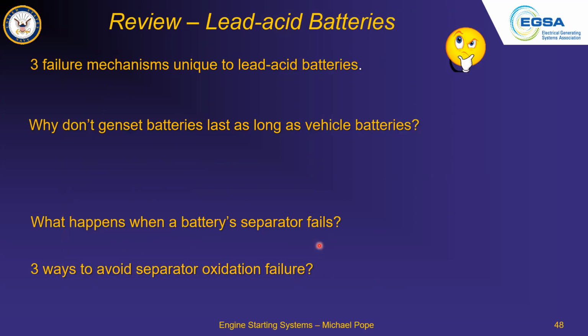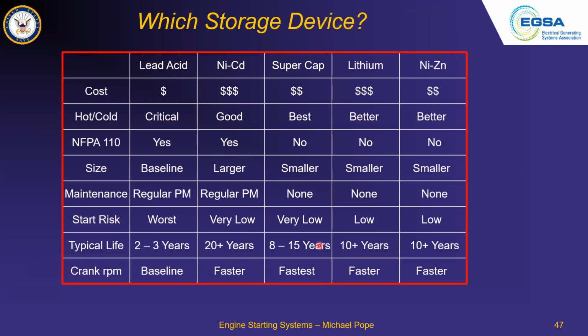Okay. With regard to the NFPA 110, so it's not in compliance with that? What would be the reason? NFPA made a decision many years ago, I guess, that critical facilities have to have total reliability. And that is why they specified this sort of safety margin, I suppose, that they wanted to make sure that the battery would last longer than the first cranking event. And most batteries do meet that criteria. So that was the main reason, to prove that it was suitable for doing at least 3 starts. And if it wouldn't start after 3 attempts, then the problem is likely the battery. So that was the basic reason that NFPA picked those 2.